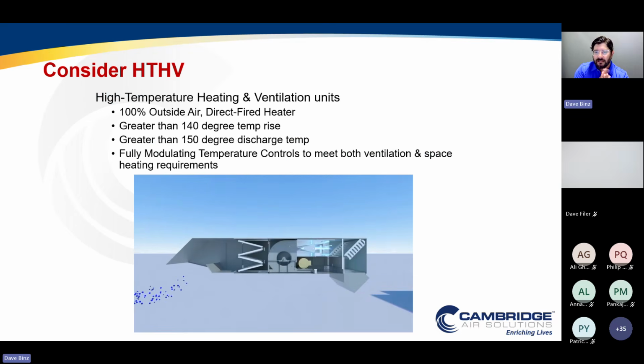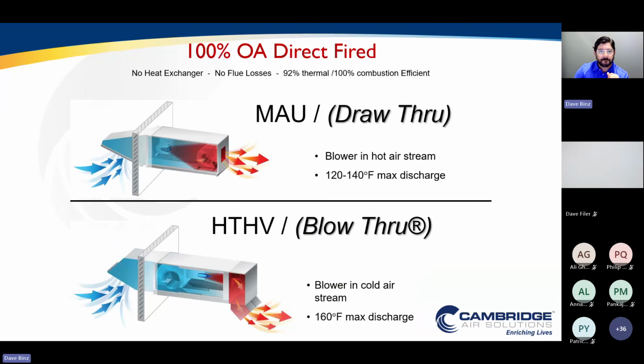The technology we often use in these large warehouses is what we call HTHV, or high temperature heating and ventilation. Similar to a makeup air unit in that it's 100% outside air. However, there are a few key differences in the system and the performance that allow us to do some really unique things from an overall built environment standpoint. That's the high temperature, meaning greater than 140-degree temp rise and greater than 150-degree discharge temperature. And again, fully modulating controls, so that I can meet my ventilation needs and my space heating needs with this modulating gas system, in a variable environment.